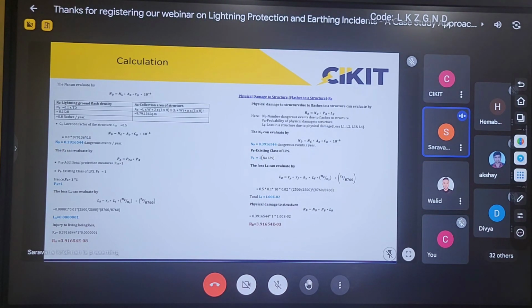RB is the parameter related to the damage of structures, whereas RA is related to injury to human beings. So if I am going for RB, the three parameters involved are ND × PB × LB. ND and PB are common, which we know from the RA calculation, and the third parameter is LB. If I perform the calculation for LB, the value is around 1E−2. If I calculate the value of RB, it comes to 10^−3. Among these two parameters, you can observe that RA is 10^−8 and RB is 10^−3.